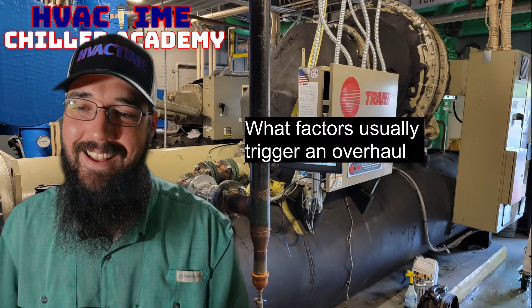What factors usually trigger an overhaul? It's going to come down to your bearings. Your bearings are going to be the number one thing in most scenarios that result in an overhaul. Now, this is if there is a failure, okay? Assuming there is a failure, your bearings are typically the first thing to fail, whether it be your thrust bearings, your sleeves, or your journals. You're going to see that in your oil analysis, and even your oil filter. You're going to start having a lot of flaking. That machine is going to have a lot of extra vibration and just operational noise that wasn't there previously. All of those things are going to point to we're starting to have a bearing issue, and we want to resolve this before we have an impeller issue. That's a whole other level of issues.